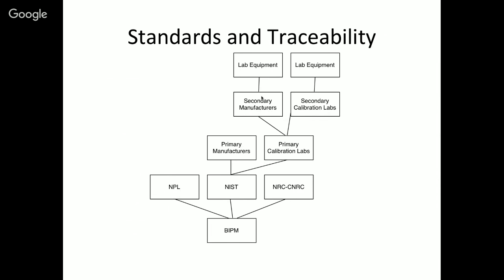Then we have secondary manufacturers. These are people like BK Precision on the electronics side, or YSI, for example, if you've ever heard of them, on the environmental monitoring side. Then you have secondary calibration labs. I used to work for one of those down in Pennsylvania. These guys use primary calibration labs to calibrate their stuff, and then in both of these cases, secondary manufacturers and distributors for those manufacturers will then send out via their distribution network. Like, for example, VWR does lab equipment, and they sometimes have calibrations done on site for them, and then they send those calibrated items out with a certification or a traceable calibration certificate. And secondary cal labs will actually come to you and do calibrations. Anyway, eventually you get up the tree all the way into the lab equipment that you or I would use.